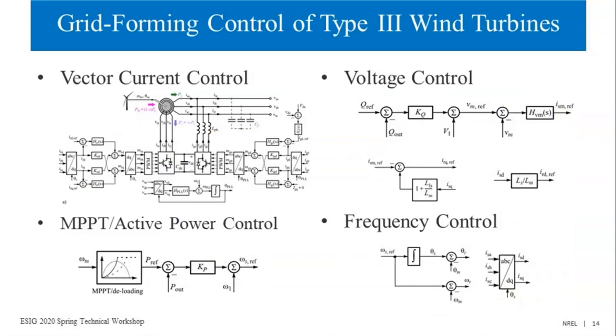Switching gears a little, this is the last topic of my presentation, and it is about the grid forming control of type 3 wind turbines. The vector current control part of a grid forming type 3 wind turbine will stay very similar to a grid following turbine, but instead of supplying current references to this current control through active and reactive power control, as in conventional turbines, for a grid forming turbine we use voltage and frequency control loops to supply these current references.